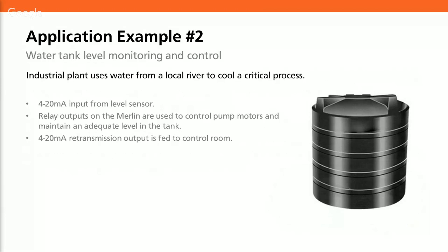So in this scenario, the Merlin is measuring the level in the tank from a 4 to 20 milliamp input, and it's using the two relay outputs to control pump motors to pump water into the tank. Again, we're also going to use the 4 to 20 milliamp retransmission output to go to a control room where someone might be measuring the level of water in the tank, and they can keep an eye on it. Okay, so let's have a look at this one with the ToolBox.